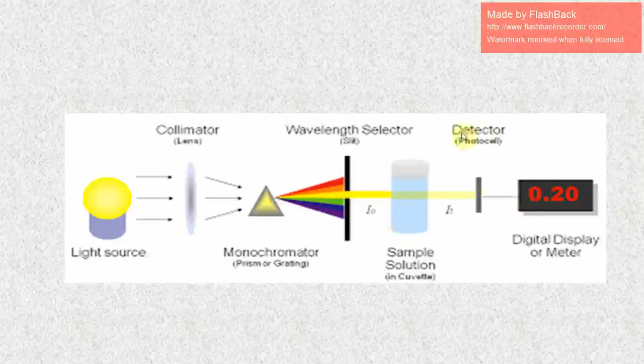A single ray of monochromatic light is passed through this slit. This is the wavelength selector, and it has the same wavelength. It passes through the sample holder, a sample solution present in the cuvette, and the amount of light which is absorbed and the amount of light which is transmitted is recorded in a detector, and a digital display displays the optical density.